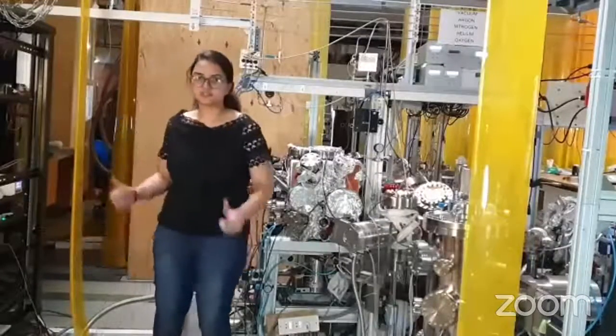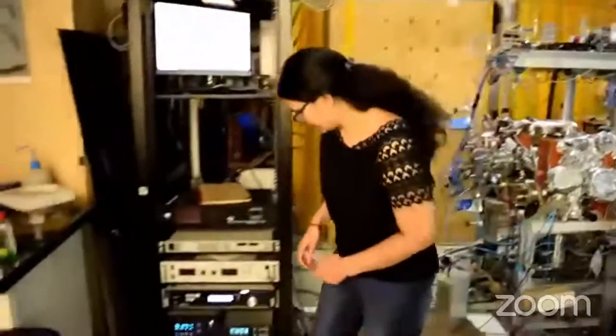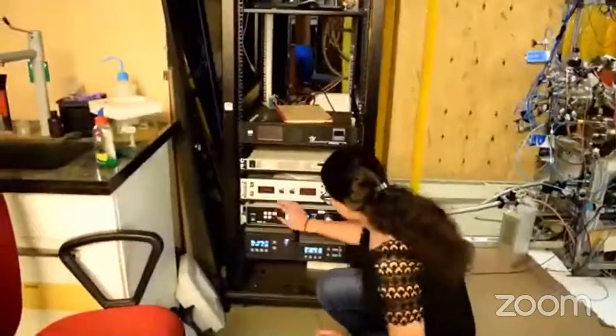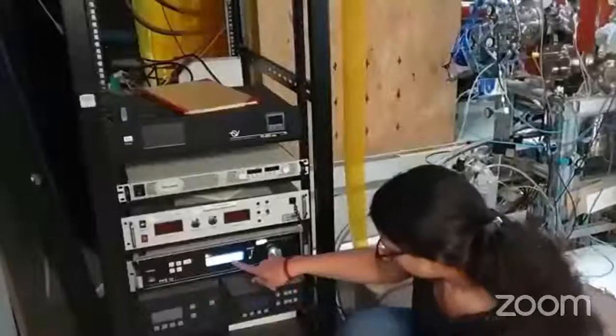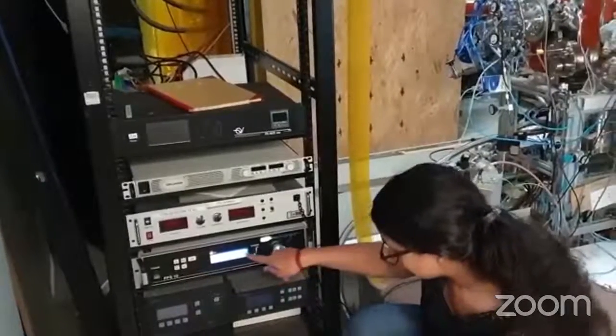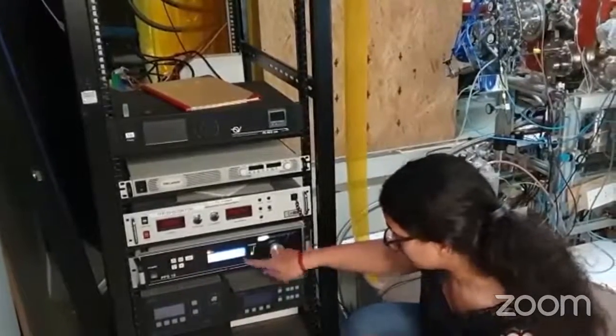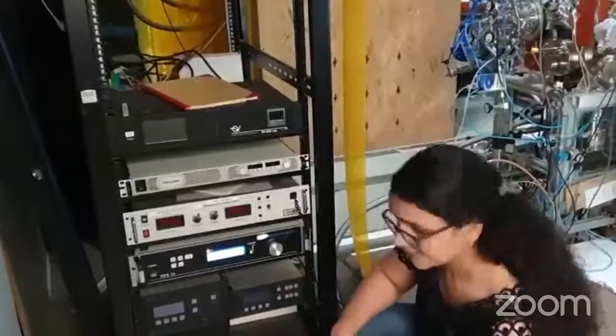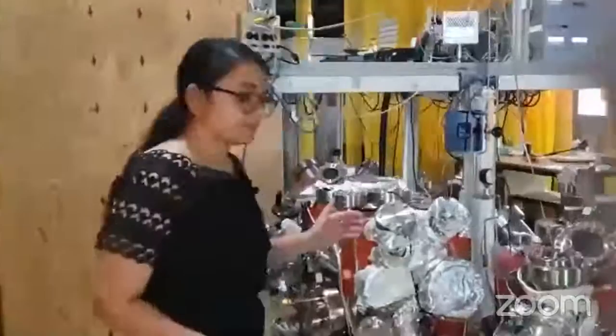Now we just have to switch on the power supply and create the plasma. Okay, let's go there. Now I am switching on the high voltage. You can see this current is coming. This is basically plasma current. This is around 123 milliamp. Now we can go to the chamber and check our plasma. There is the sample we have mounted in the load lock, and this purplish color is plasma.